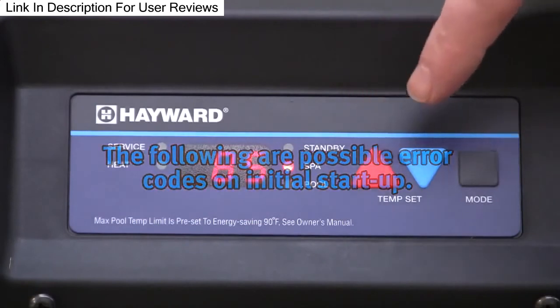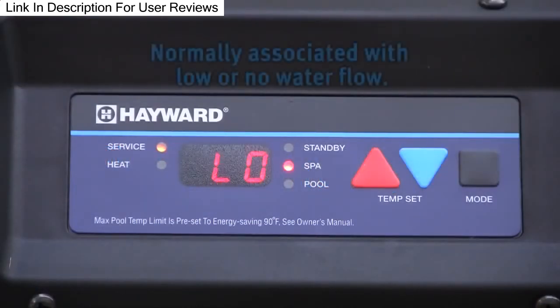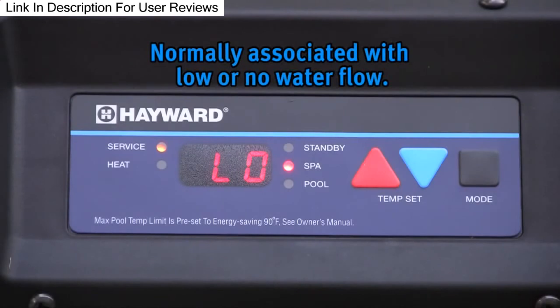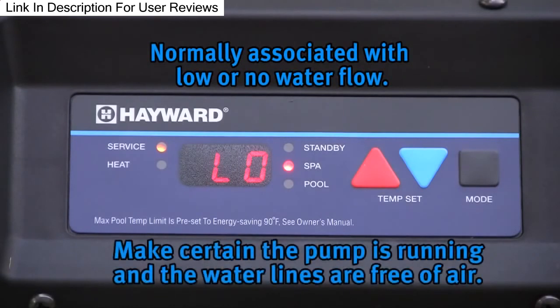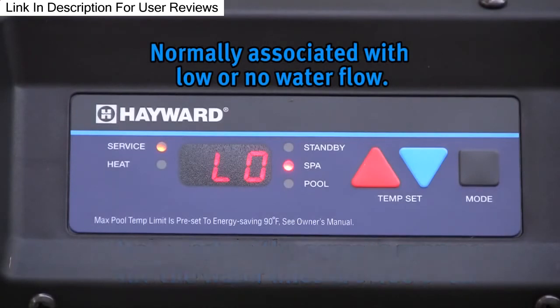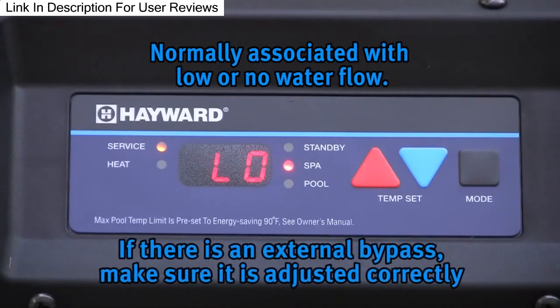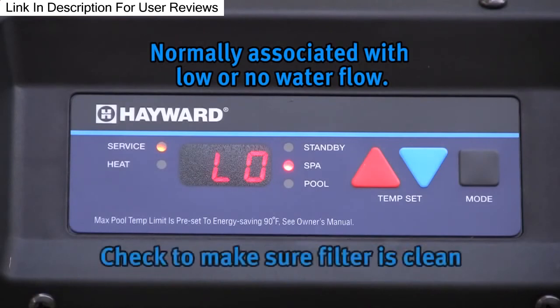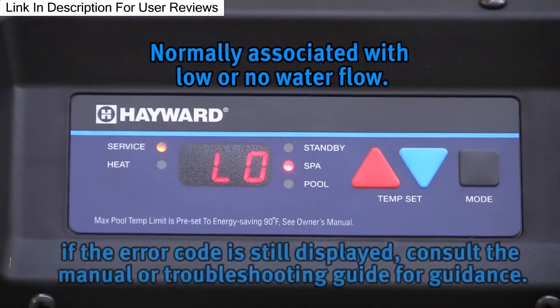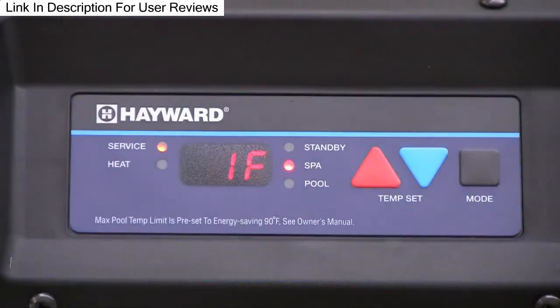The following are possible error codes when first firing the heater. LO. This is normally associated with low or no water flow. Make certain the pump is running and the water lines are free of air. Allow a few minutes after turning on the pump for this error to clear. This allows time for the pump to prime and the air to be cleared from the lines. If the heater has an external bypass, it may need to be adjusted to allow sufficient water flow through the heater. Check to make sure the filter is clean. If this is not the problem, consult the manual or troubleshooting guide for further troubleshooting instructions.